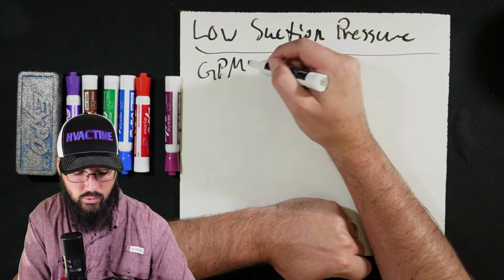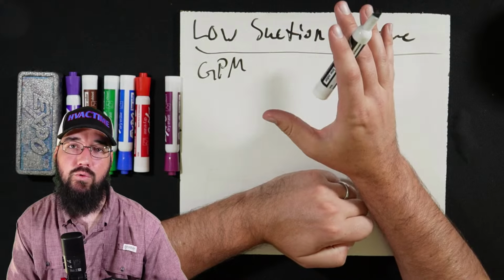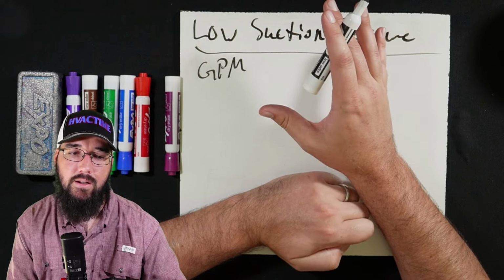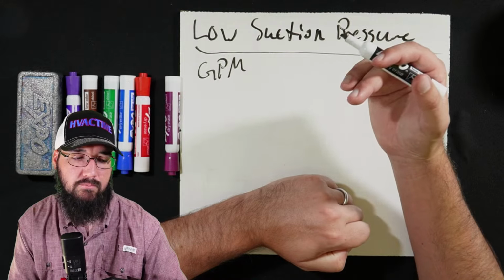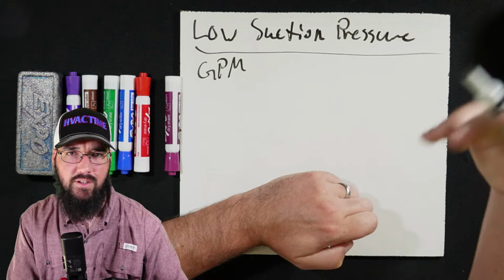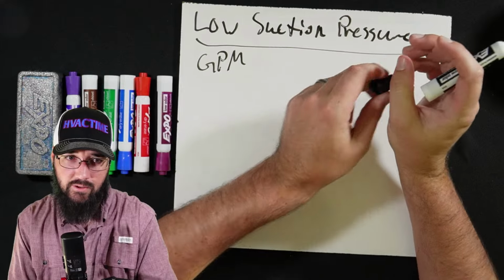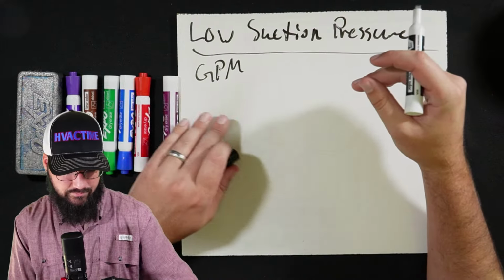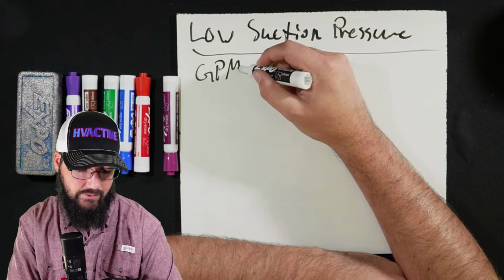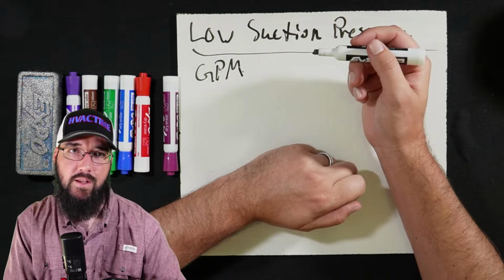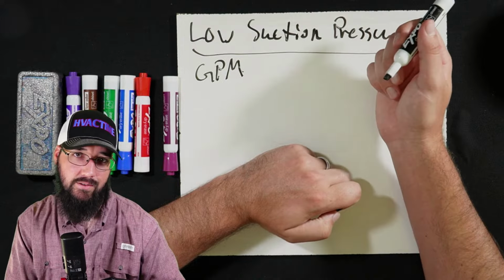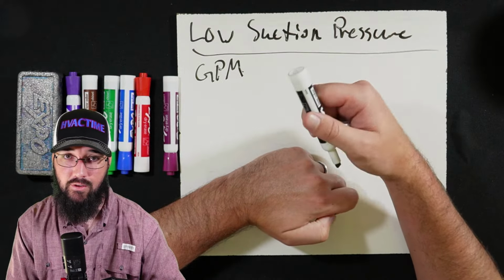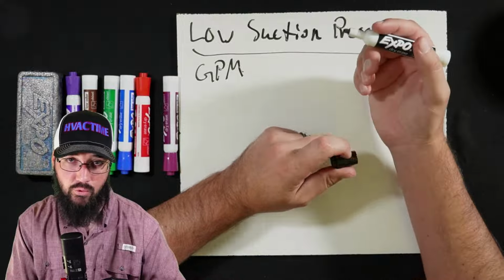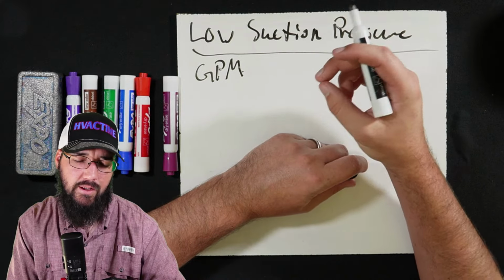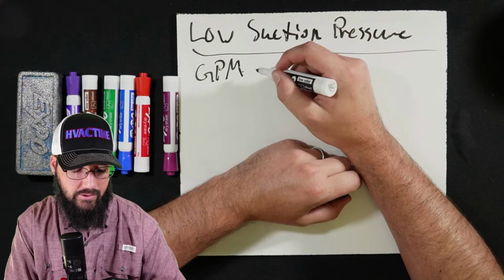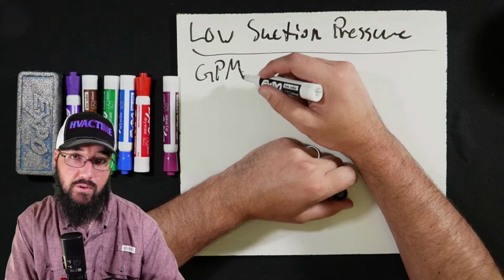So this is an air-cooled machine. RTAC is an air-cooled screw produced by Trane. It's one of their newer screws. I guess it replaced the RTAA series. It was a great machine, still is. I'm a big fan of the RTAC. It's been replaced now by the RTAF, which replaces the RTAC in new machines, so you're not going to see new RTAEs or RTACs out there. But anyway, GPM is the first thing we need to verify.